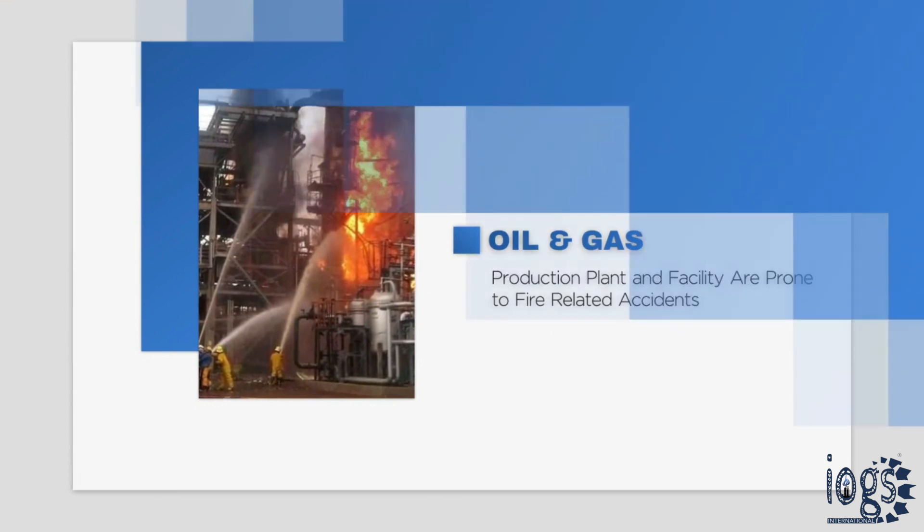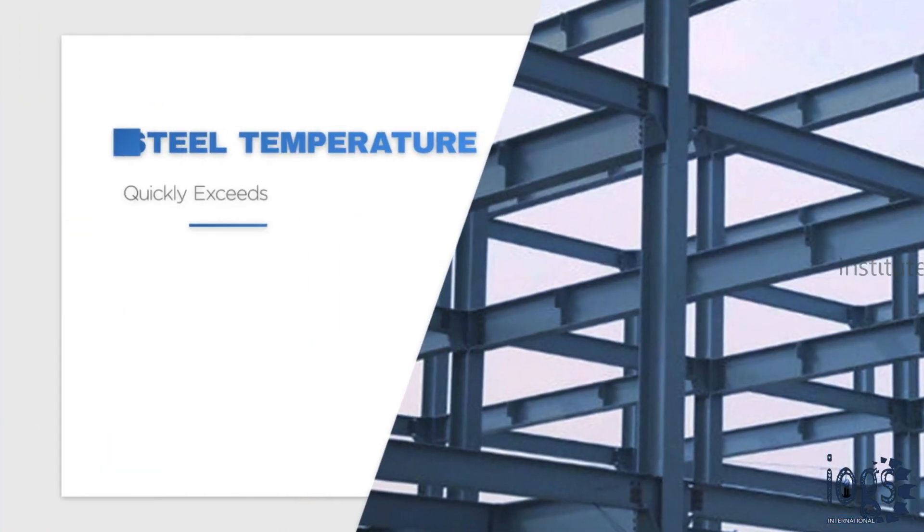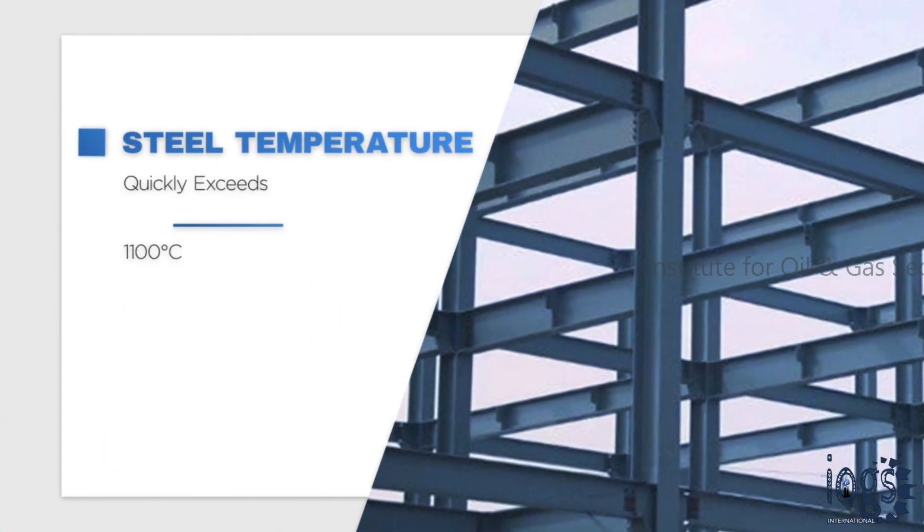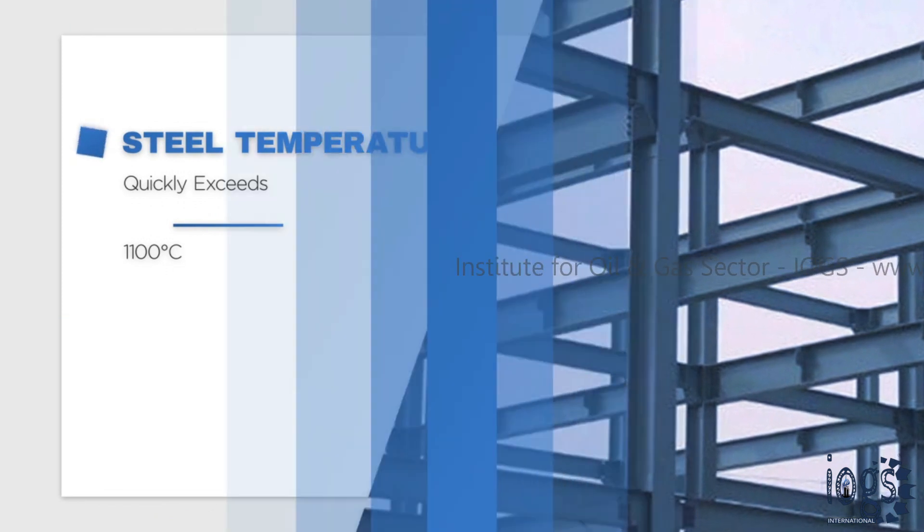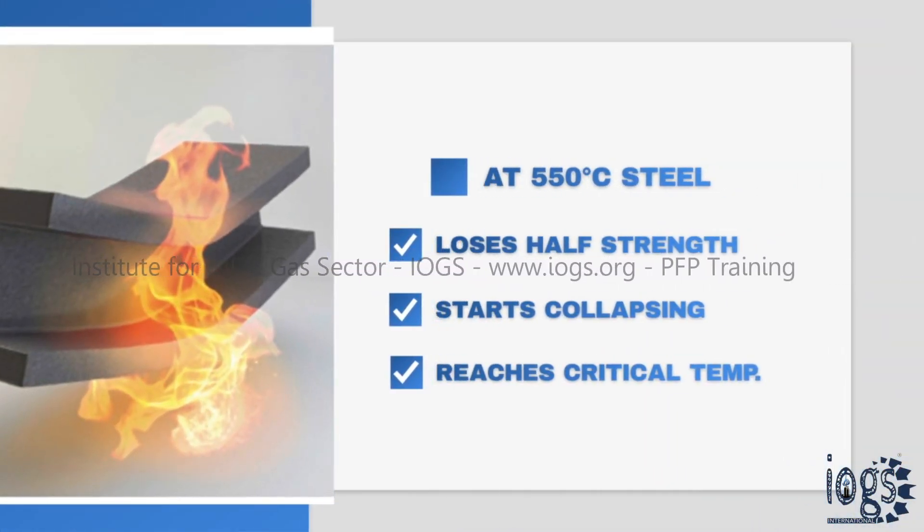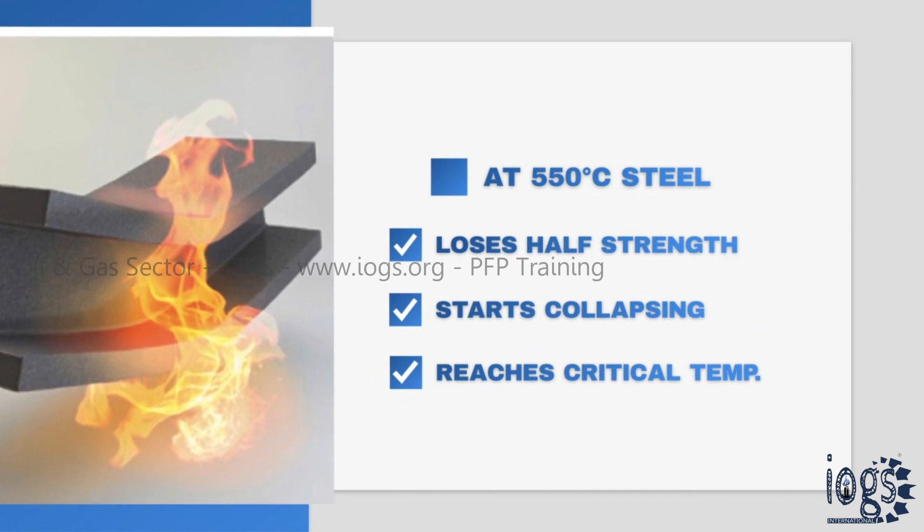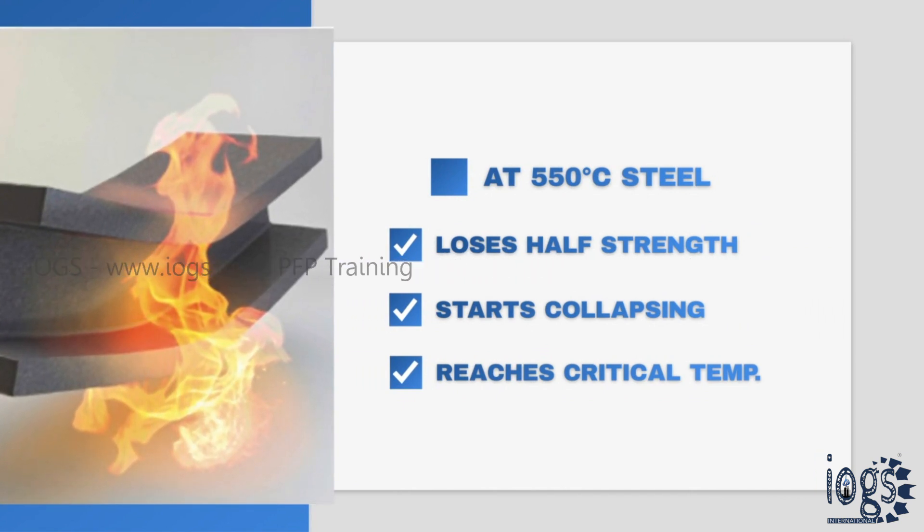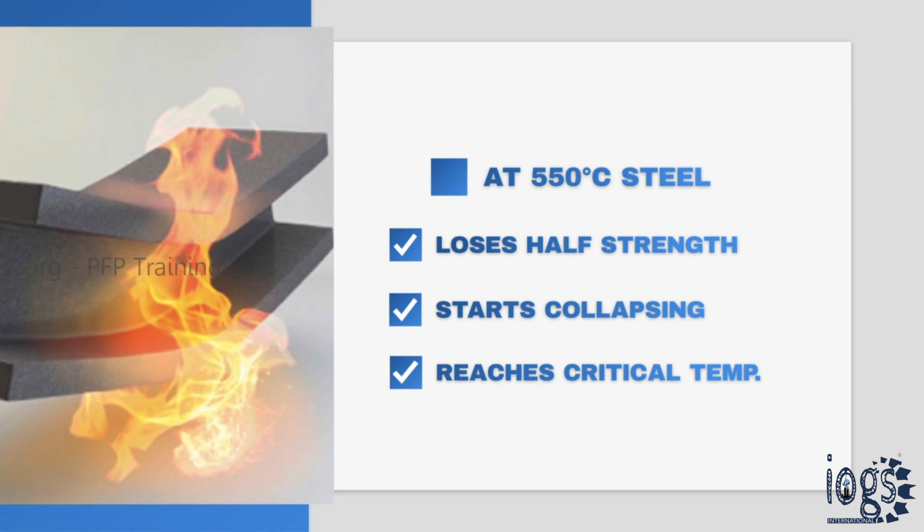In the case of a fire incident in a steel-made facility, the temperature can be as high as over 1,100 degrees Celsius. When the temperature gets to 550 degrees Celsius, about half of the original strength of steel is lost. It is at this critical temperature that load-bearing steel starts to collapse.